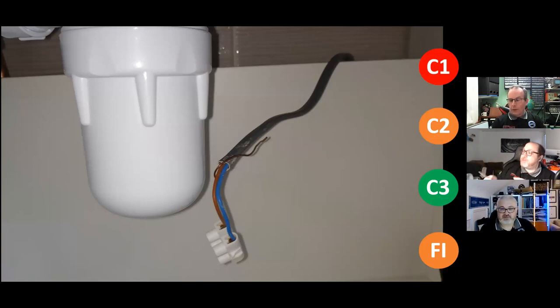It's too dangerous though. What happens is they do that to test it, but then they leave it because obviously the other trade hasn't put in the system and it gets left. It's been stripped and terminated for testing. Looking at that, you can see the CPCs there for the R1 plus R2 testing, but it's just been left there, abandoned. There's a valuable bit of guidance there for the person signing off that certificate. When you are signing off that the installation is complete, make sure it is complete, and there's not a few variations that the builder's waiting on that you're doing on trust, because these sorts of things happen.